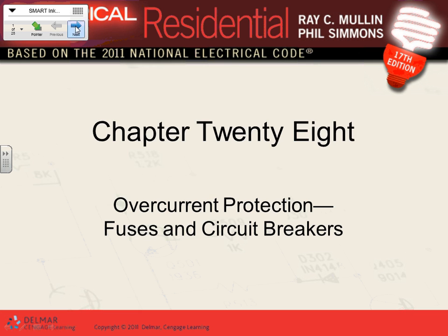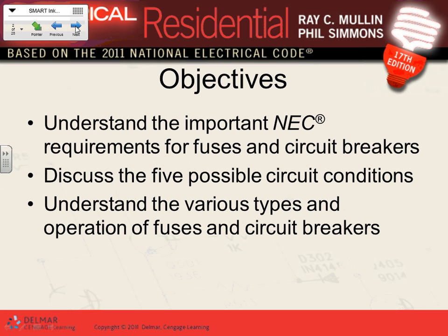So we're going to talk about overcurrent protection only. If you have the luxury one day to work on power, and you get involved with the engineers that work on the high voltage distribution lines, there is more than overcurrent protection for the power system. We wouldn't touch on that unless you go work for utilities. There's over-under voltage protection, over-under frequency protection, directional overcurrent protection. There are close to 100 things you need to take into consideration when you protect an operating power system. In the code and in the low voltage system, 600 volts or less, for the most part we focus on overcurrent protection. That's it, fuses and circuit breakers.